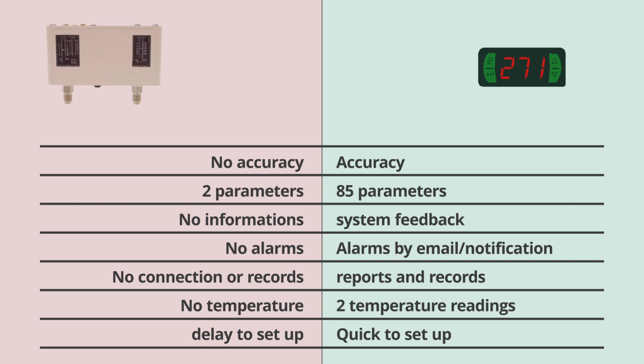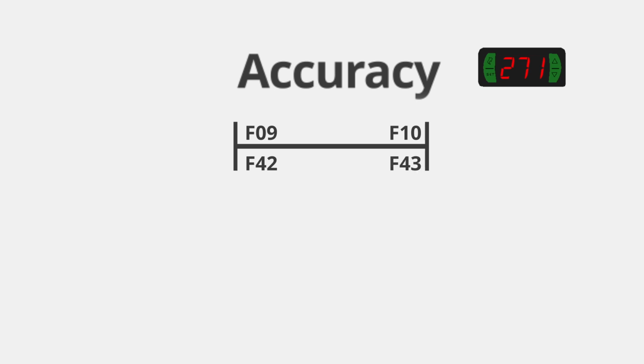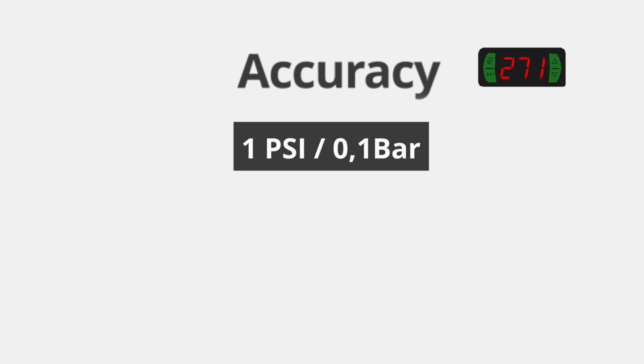Probably the first difference you would notice is the controller's accuracy. When the work range of the transducer is correctly configured on functions F10 and F9 for sensor 1, F42 and F43 for sensor 2, the degree of precision is unparalleled.